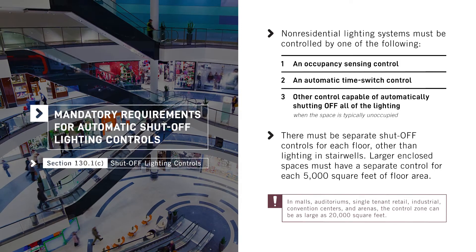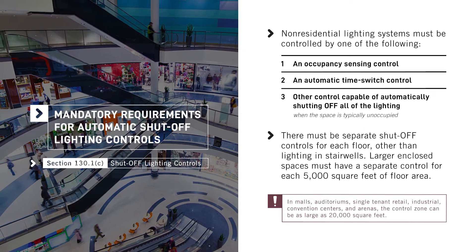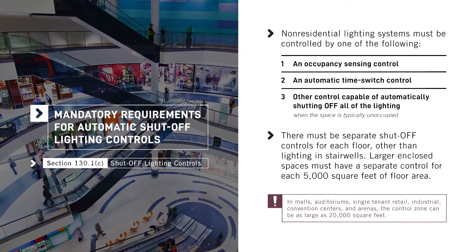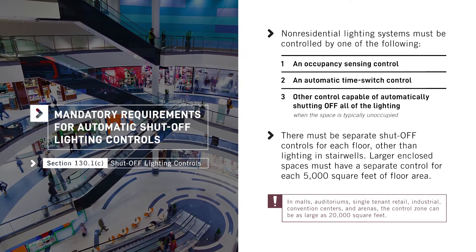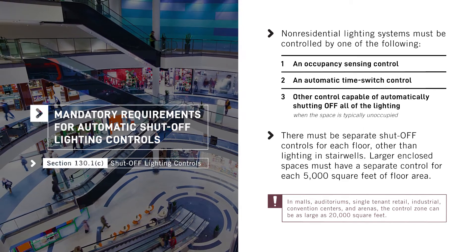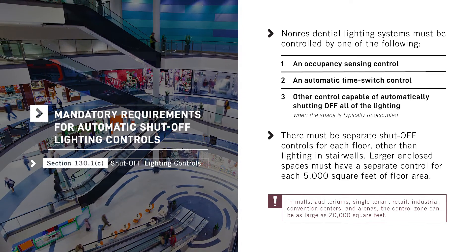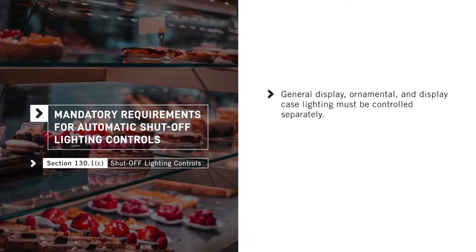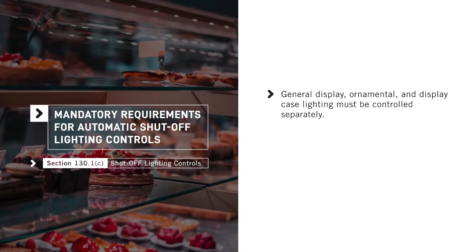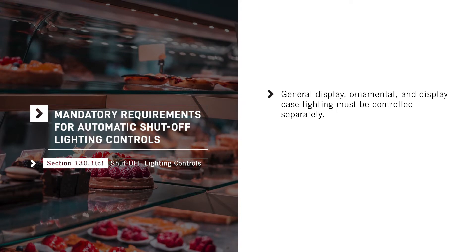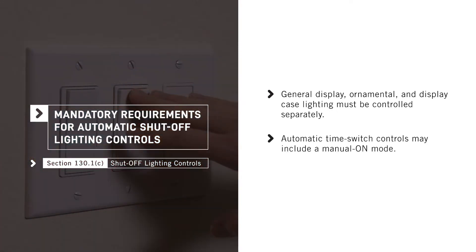However, in malls, auditoriums, single-tenant retail, industrial, convention centers, and arenas, the control zone can be as large as 20,000 square feet. General display, ornamental, and display case lighting must be controlled separately, and automatic time switch controls may include a manual on mode.